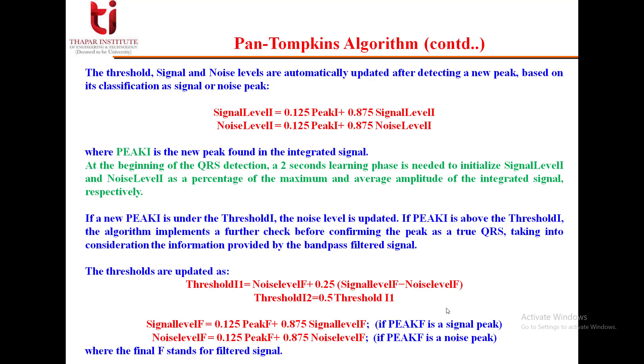Threshold 1 is calculated as: threshold_1 = noise_level_1 + 0.25·(signal_level_1 − noise_level_1), where noise_level_1 is the running estimate of the noise level in the integrated signal and signal_level_1 is the running estimate of the signal level. The threshold and signal and noise levels are automatically updated after each new detected peak based on whether it is classified as signal or noise. Signal level and noise level are updated as: signal_level_1 = 0.125·peak_1 + 0.875·signal_level_1, and noise_level_1 = 0.125·peak_1 + 0.875·noise_level_1, where peak_1 is the new peak found in the integrated signal. At the beginning, a 2-second learning phase initializes these levels as percentages of the maximum and average amplitude of the integrated signal.